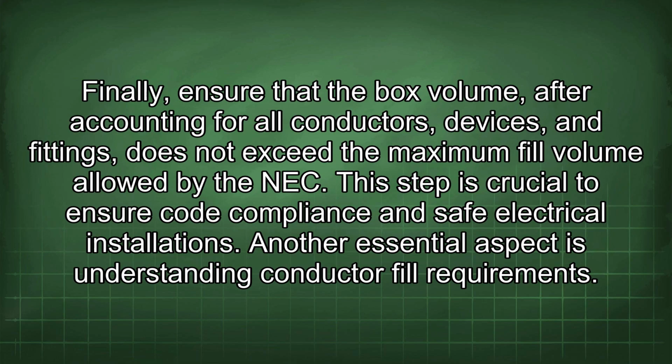Finally, ensure that the box volume, after accounting for all conductors, devices, and fittings, does not exceed the maximum fill volume allowed by the NEC. This step is crucial to ensure code compliance and safe electrical installations.